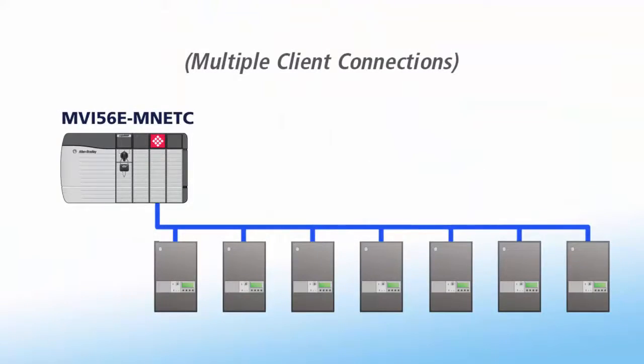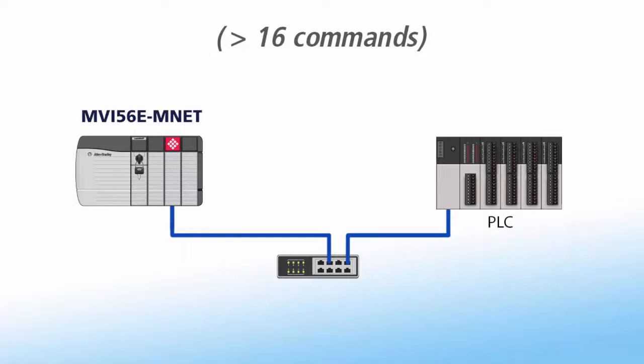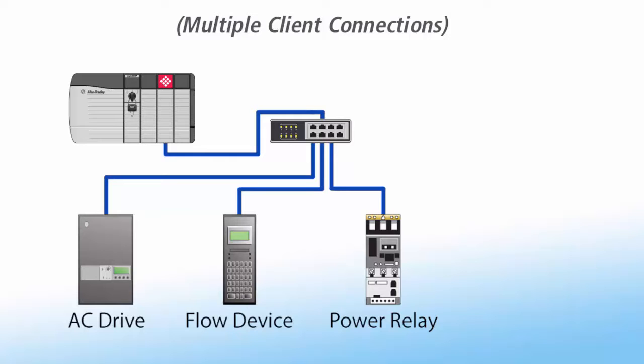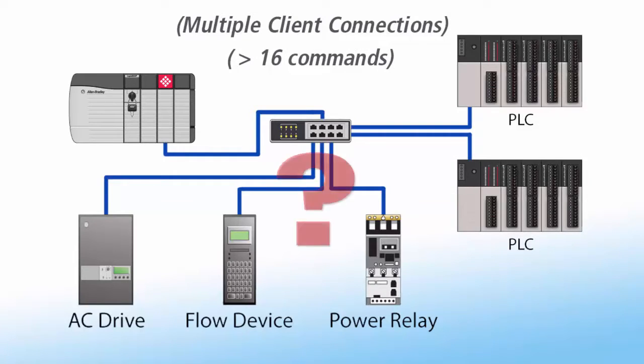In conclusion, if you have multiple Modbus TCP/IP server devices that you need to communicate with, go with the MVI56E MNET-C. If you need significantly more than 16 commands for your client connection, consider the MVI56E MNET. If you intend to use the module in a remote rack via ControlNet, use the MNET-R or MNET-CR. If your application is more complicated, like you need multiple connections and more than 16 commands per connection, contact our technical support for help figuring out your best option. Thanks for watching.